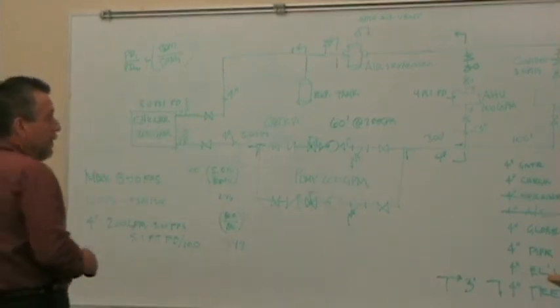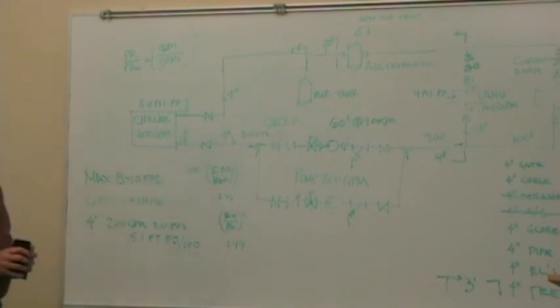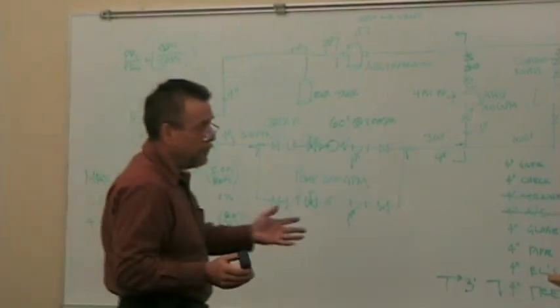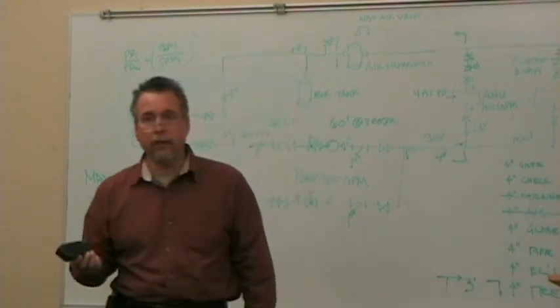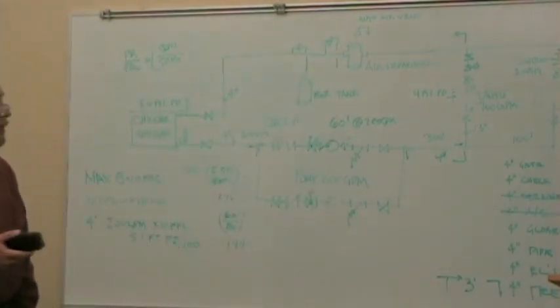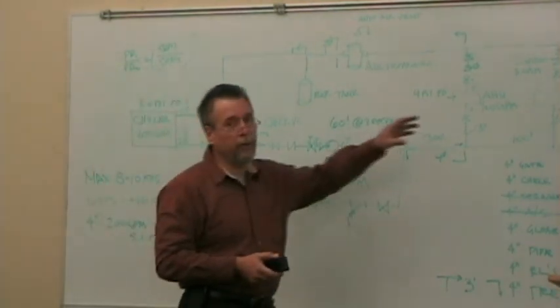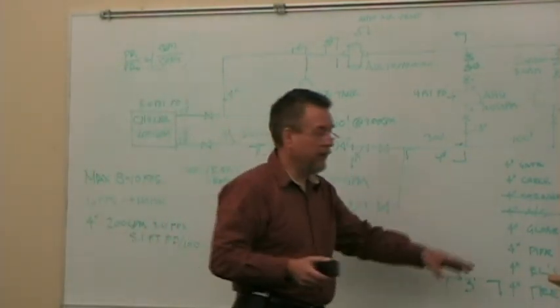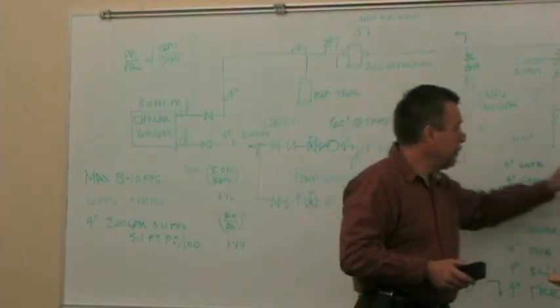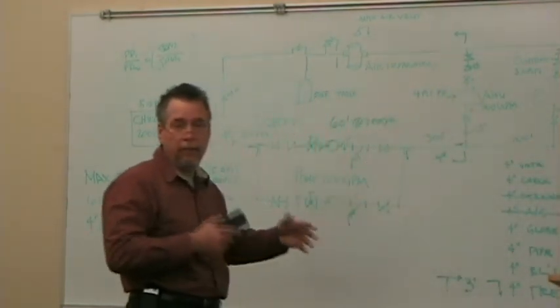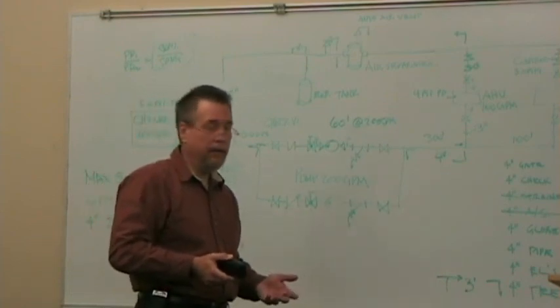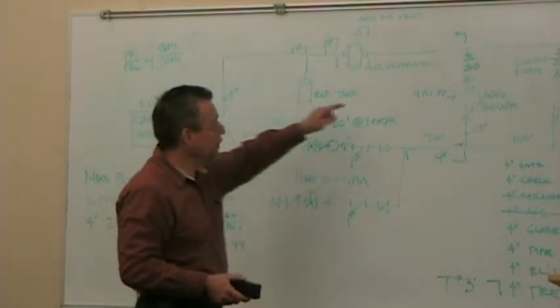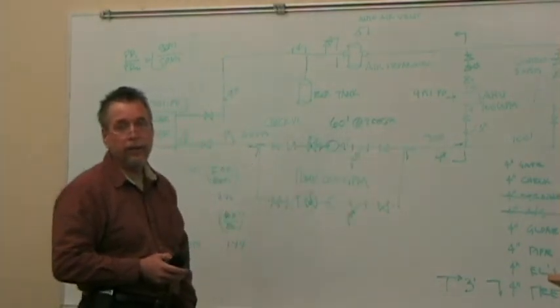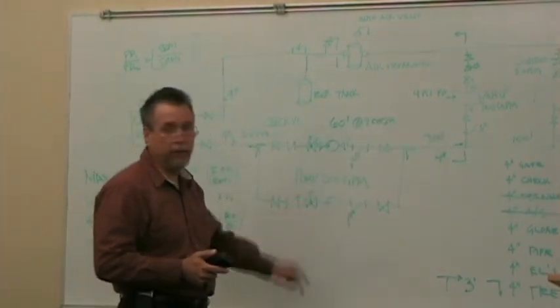Okay. Are those values pretty representative regardless of pipe size? The ratio is going to be about the same if we're dealing with a 2-inch system or a 12-inch system. Most HVAC systems operate in the 60 to 100 feet of head range. But comparison of fittings versus pipe, yeah. And that's the point I was trying to make, is my pipe and elbows and T's. A lot of people get real concerned about adding an elbow. It's insignificant, but these big devices are here, these coils, pressure drop, strainers, and check valves.